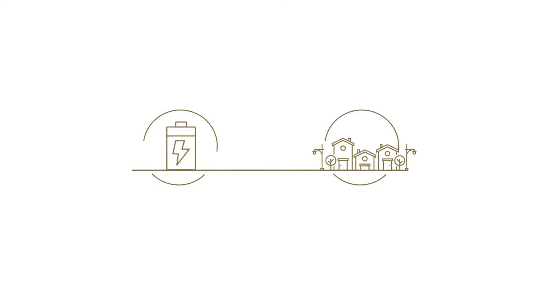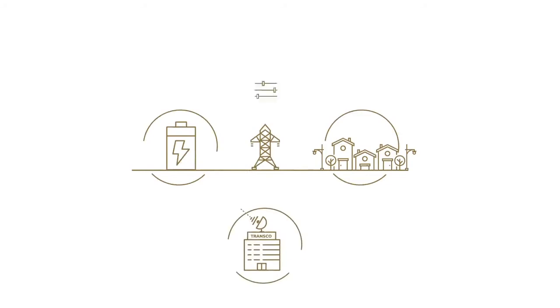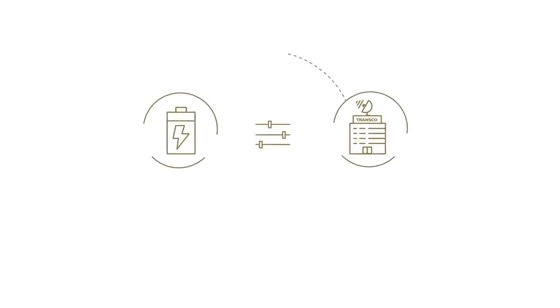The NAS battery system exchanges reactive power through 11 and 33 kilovolt transmission lines to stabilize voltage fluctuation upon receipt of a signal from the TRANSCO load dispatch center. The NAS battery also performs frequency control in coordination with the existing load frequency control equipment in the Central Load Dispatching Center.